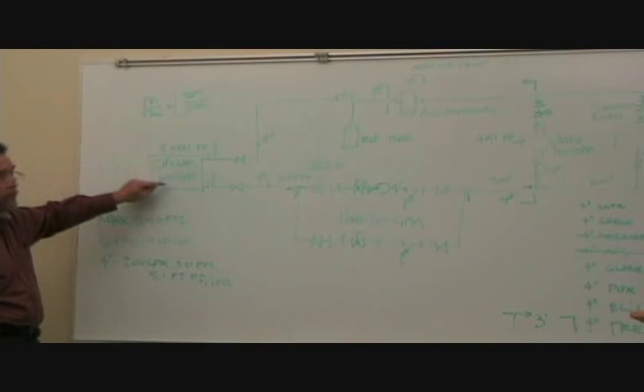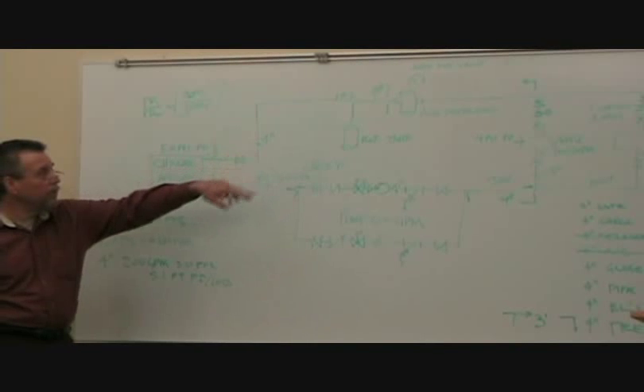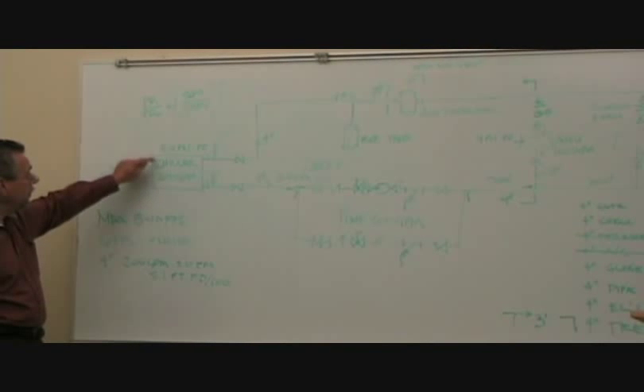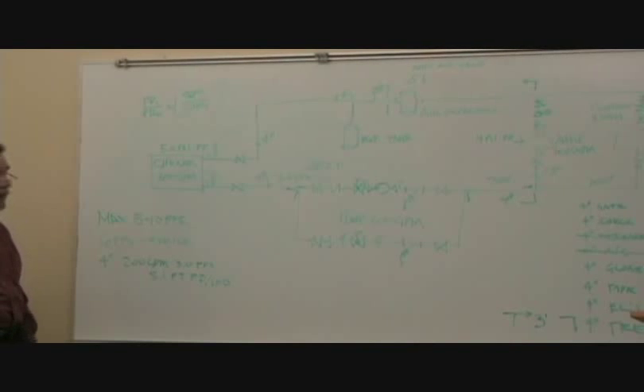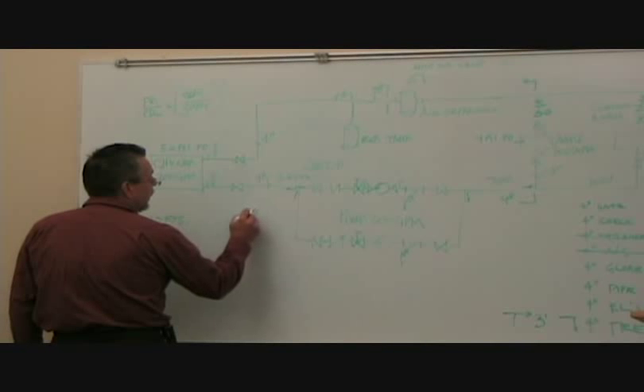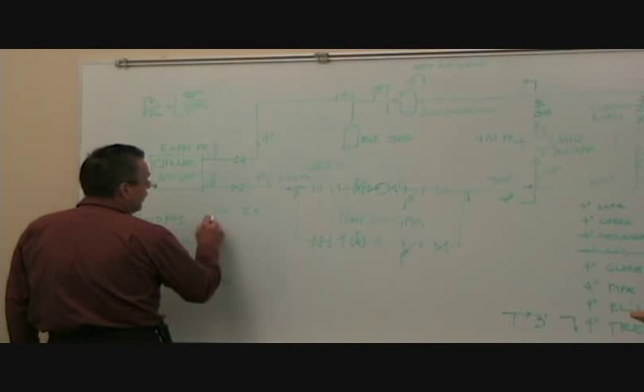I know that this is going to be a lot less. If I measure 4 pounds, I know that's going to be a lot more. On a clean chiller, I should be able to determine what my system flow is just by coming to this point and measuring the pressure drop. And that's just, if I have these two known data, then I can measure that. So I know that my P1 is 5 at 200 GPM, but I measure 3 pounds.